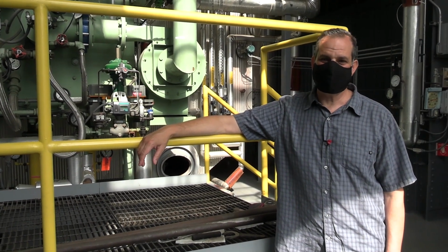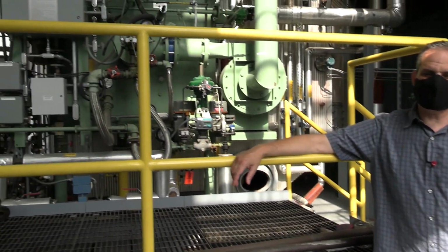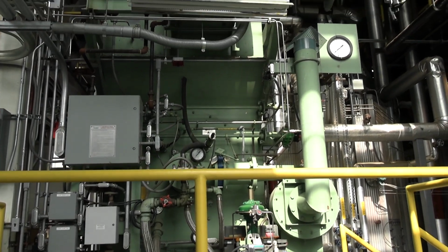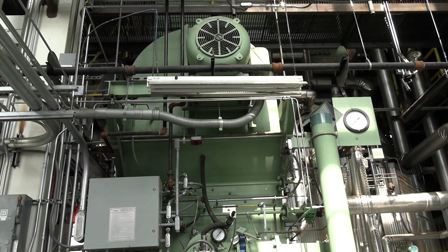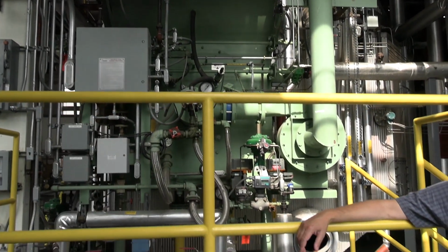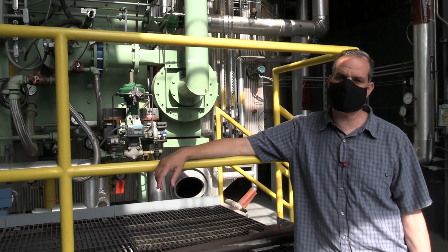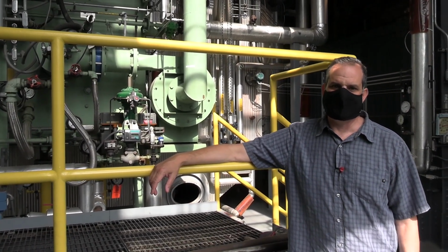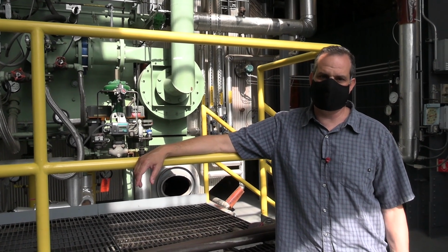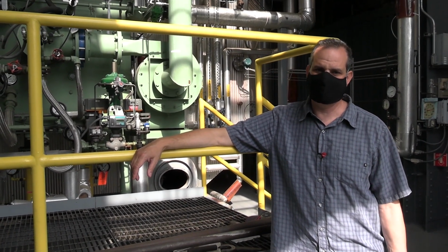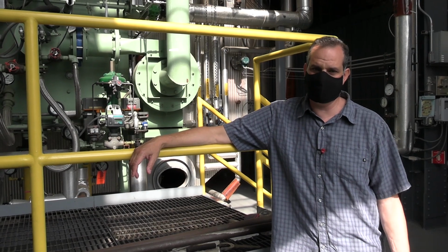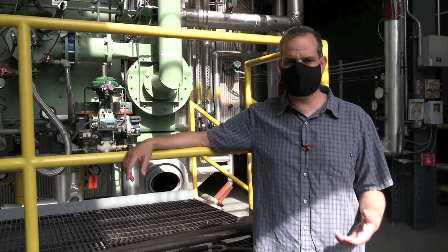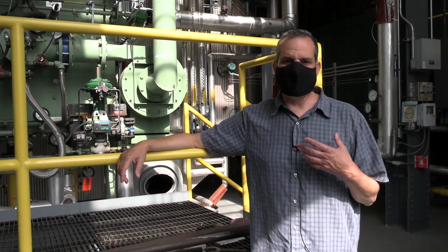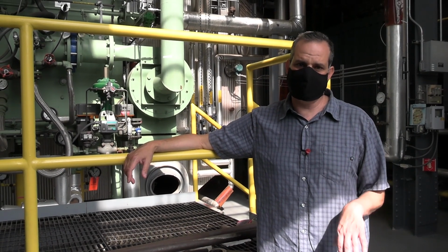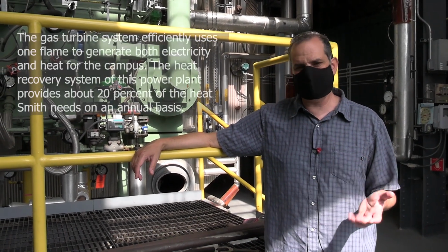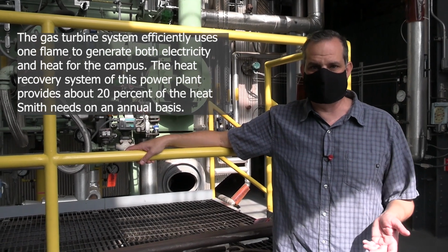Behind me, this is a boiler. Smith has 3 large boilers that also feed the heating system. We talked about the heat recovery steam generator — that's what we try to use first, because that way we're really taking advantage of the higher efficiency of cogeneration. We have one flame, we're making electricity, and we're making heat. That heat recovery system provides about 20% of the heat we need on an annual basis.